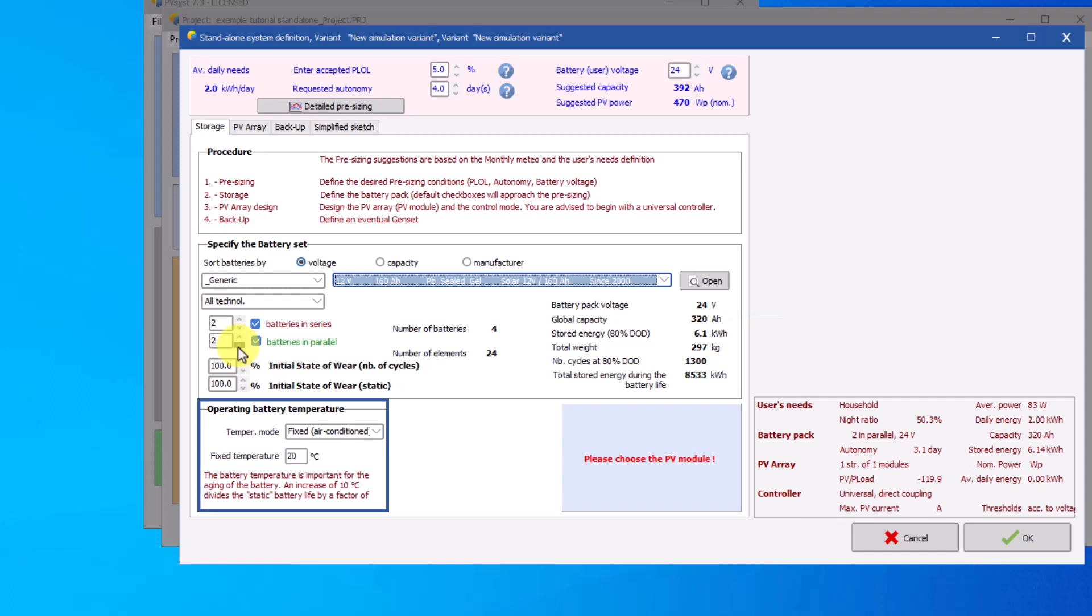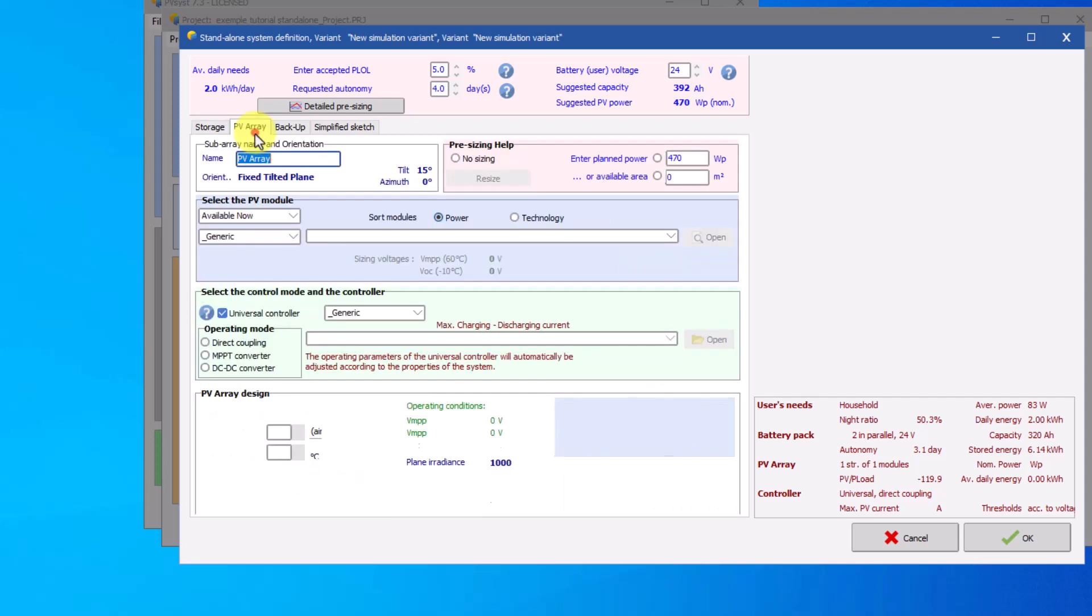A final parameter to consider is the temperature of the batteries in operation. The temperature is important for the life of the battery. An increase of 10 degrees decreases the static lifetime by a factor of 2. The storage configuration is complete. Proceed to the PV array configuration.